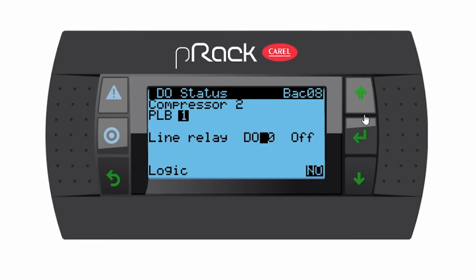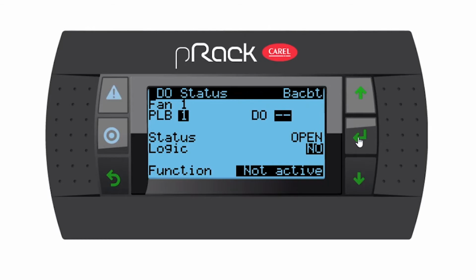Compressor 2. Let's make that number 2. It's going to be normally open. Go down. Compressor 3, I'm going to make 3. Normally open. Go down. And compressor 4, I'm going to make it 4. And normally open. Perfect. Fan 1. Now we have to assign fan 1. So let's assign fan 1 to DO5. It's going to be normally open. And the function, as you can see, is not active. Remember, when the rack is running and you have outputs that are active, it will show you on this page that the controller has switched on that relay, so it will show active.